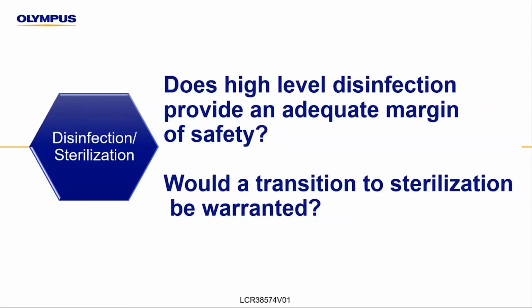So the clinical data supports exactly what Dr. Cote was saying. I don't think it's a silver bullet that if you put everything through ETO sterilization you're going to ensure that everything in that scope is sterile, because you won't. And there's certainly data out there to show that if cleaning is inadequate or if biofilm is allowed to form with wet storage and you get biofilm forming inside the channels, sterilization will fail as well.